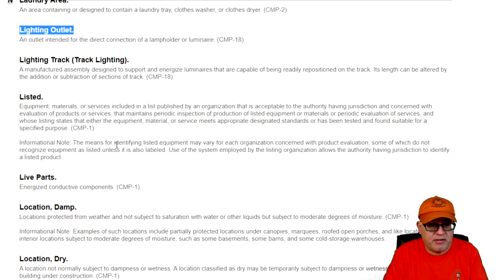So in this example, what is a lighting outlet? It's an outlet intended for the direct connection of a lamp holder or luminaire. So a lighting outlet, whether it's on the wall or on the ceiling, has the wires in the outlet box. That's why they call it an outlet box. Okay, and you're going to put a luminaire on it. And a lamp holder, incidentally, is like a keyless, which is just a keyless with a lamp, which people refer to as a light bulb, but it's a lamp.